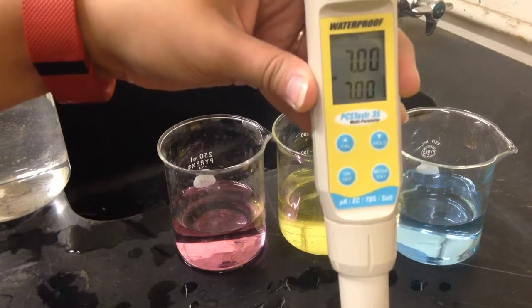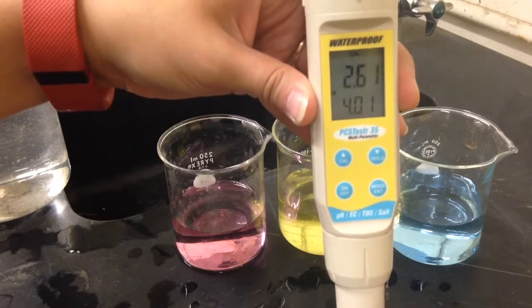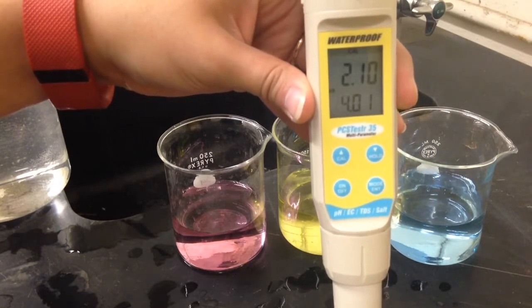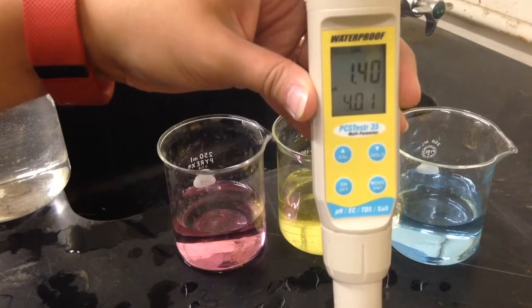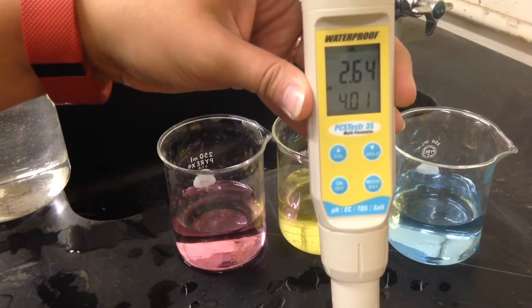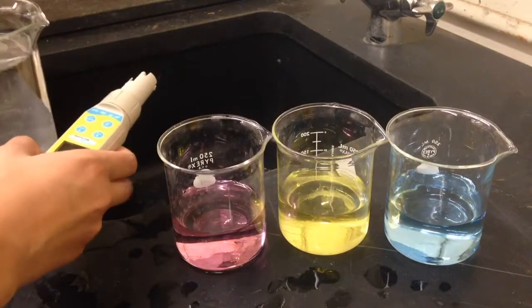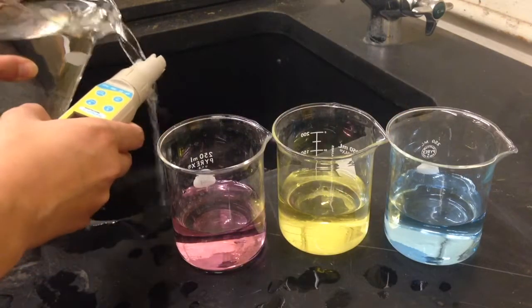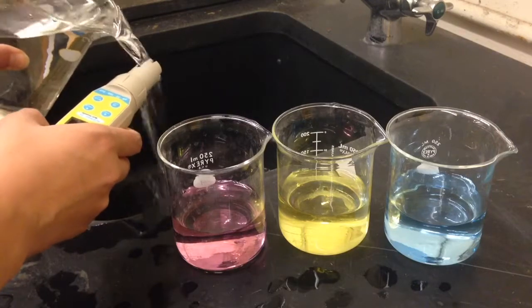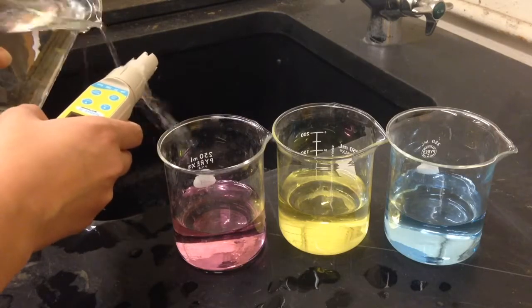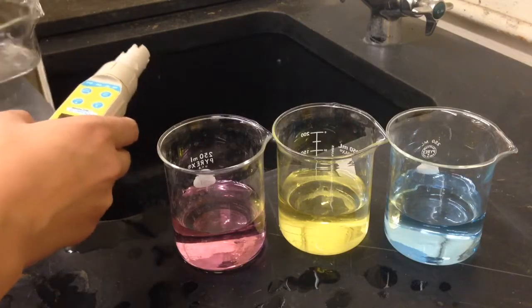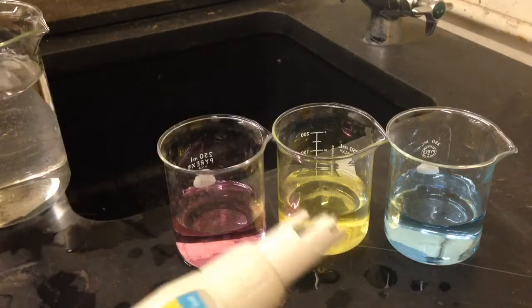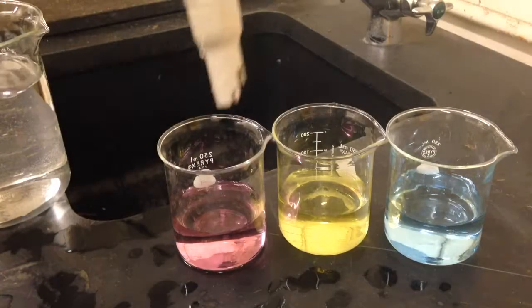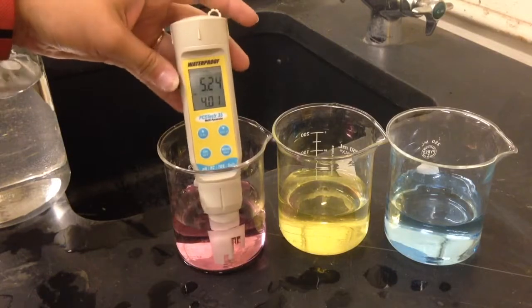The primary display will flash, and the secondary display will show the other calibration standards in which we can calibrate our meter. Before we can use either of those standards, we need to rinse our meter. So I'm going to rinse my meter 3 times with the tap water. We can use either the acidic or the basic solution next. So we will choose one and immerse our meter.